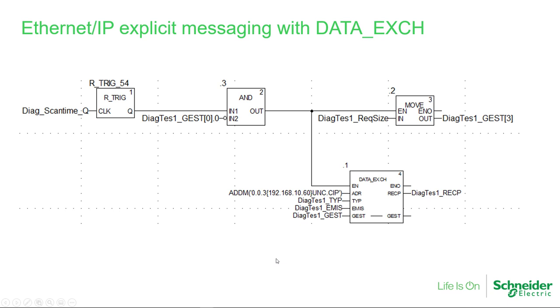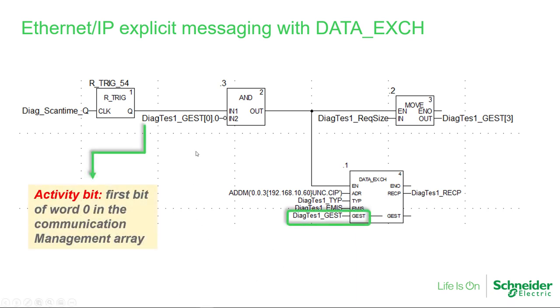Two solutions are available to implement Ethernet IP explicit messaging. One is the data exchange function block. There is an activity bit related to the status of the function block, shown in this example being used to ensure the transaction has finished before triggering it again.